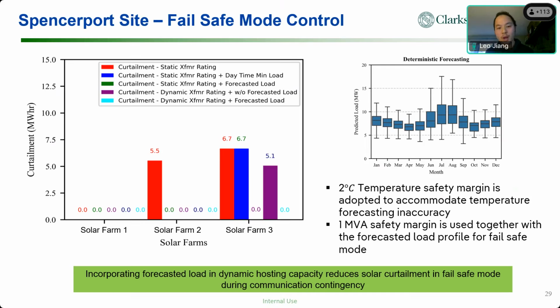Then if you compare the red bar to the blue bar, for example, the blue bar is the static transformer rating plus the daytime min load. For this site, if I remember correctly, the daytime min load is about 3 megawatt, roughly, I think it's 2 point something. Then for your second solar farm, because it has 7.6 megawatt of static hosting capacity, if you add about 3, then in the fail-safe mode control solar farm 2 will not really face much curtailment, because it has the limited 5 megawatt output, which is the maximum output from the site.